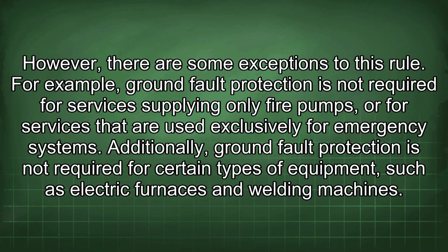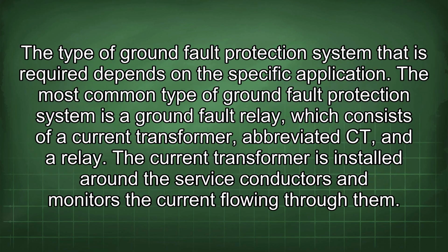For example, ground fault protection is not required for services supplying only fire pumps, or for services that are used exclusively for emergency systems. Additionally, ground fault protection is not required for certain types of equipment, such as electric furnaces and welding machines. The type of ground fault protection system that is required depends on the specific application. The most common type of ground fault protection system is a ground fault relay, which consists of a current transformer, abbreviated CT, and a relay.